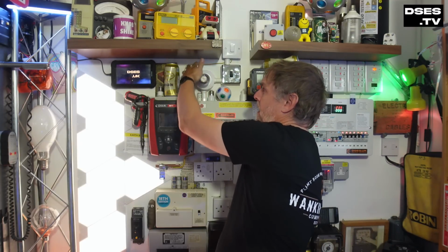James's 48 volts is more impressive than the 7 volts I can drag out here, but I'm limited to what I can demonstrate on my rig. James gets better numbers because he has a longer wiring run and his floating CPC is jacketed inside a twin and earth cable, which puts the CPC at very close proximity to the electric field of the line conductor. In my setup, I only have a few meters to play with, looped inside this box here, and my wiring is in single, so I can't wind it as tightly together as cores within the same cable would be. I've also had to run my floating CPC here on the outside, and that's just to keep it away from any working earth or neutral conductors to stop them from dampening the voltage I have managed to induce upon it.